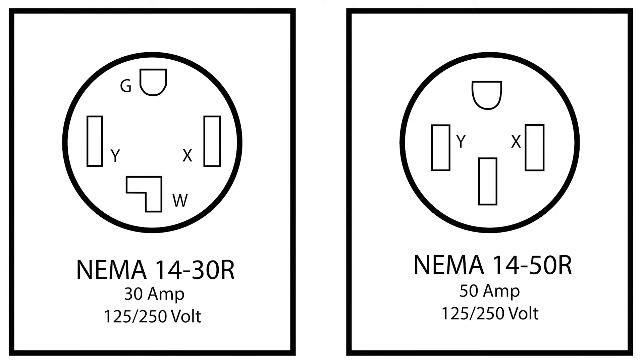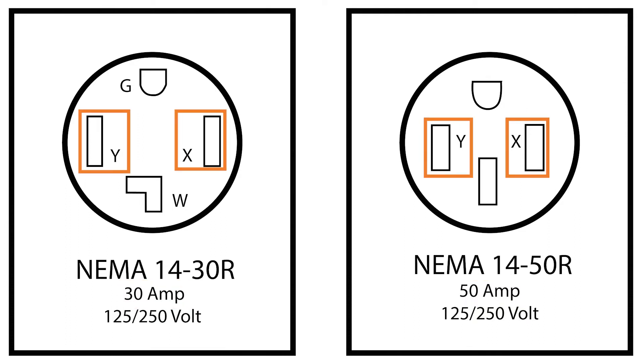As far as technical differences go, there's one big one. The NEMA 14-50R is rated for 50 amps while the NEMA 14-30R is rated lower at 30 amps. Besides that, both offer two hot wires with 125 volts each, which becomes 250 volts. This is called a 125/250 volt receptacle.